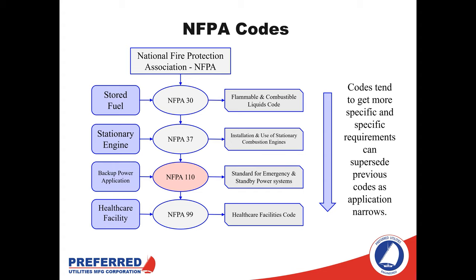Out of all those codes, most of our time is going to be spent in the National Fire Protection codes. The NFPA codes go from NFPA 30 up to NFPA 110 for the systems we're discussing, ranging from more general to more specific. NFPA 30 covers generally stored combustible liquids, but may be superseded by NFPA 37 or NFPA 110. If we see something in NFPA 110 that differs from NFPA 30, it takes precedence. NFPA 110 is the code we'll spend the most time in when designing fuel oil systems for mission-critical backup power systems.